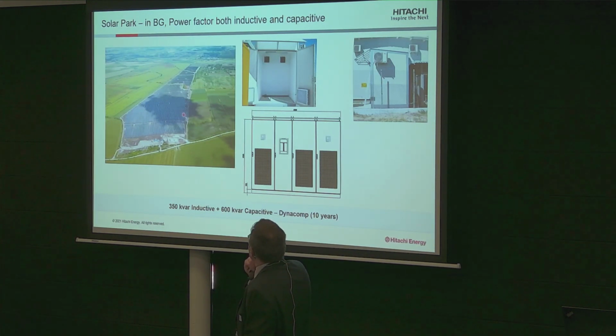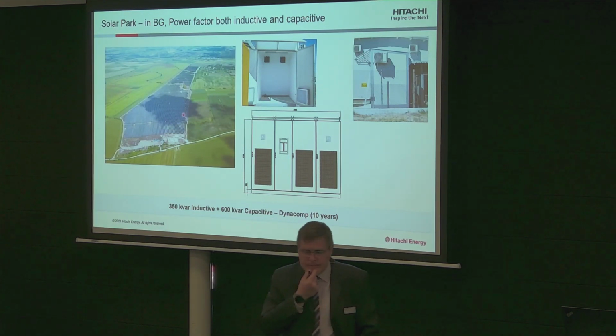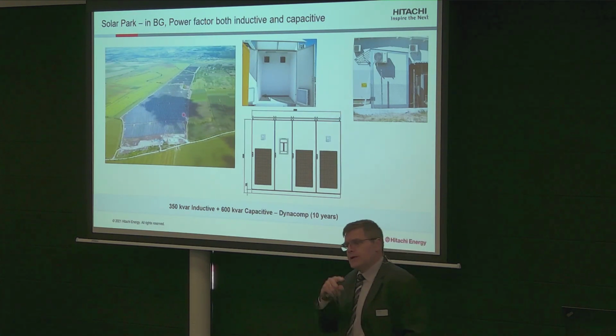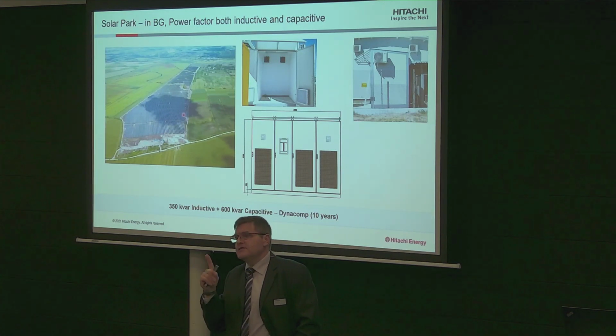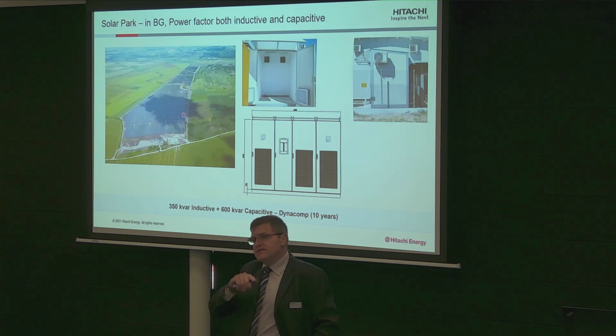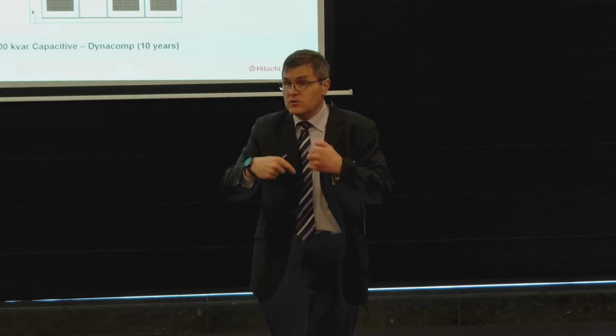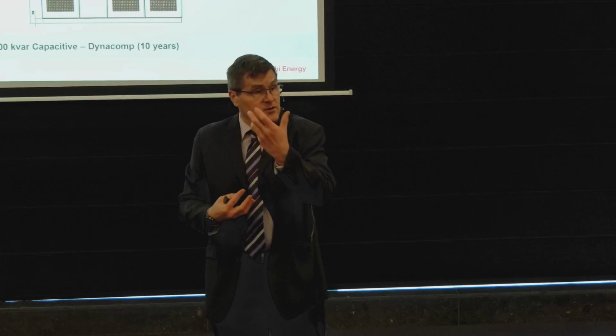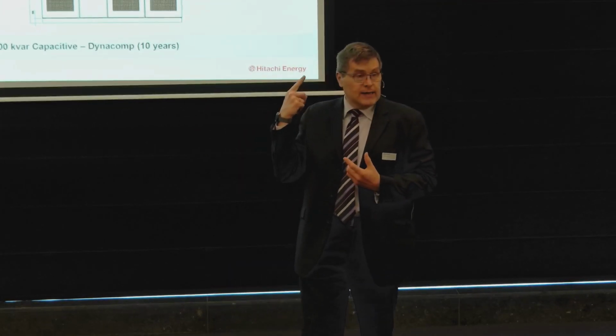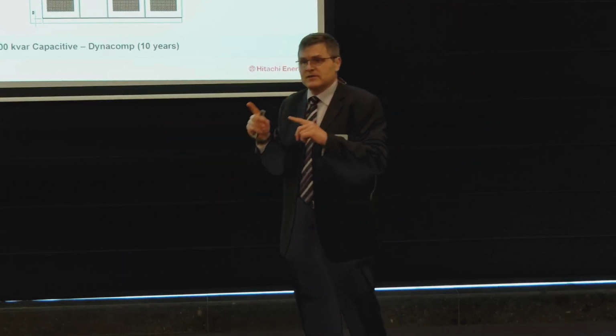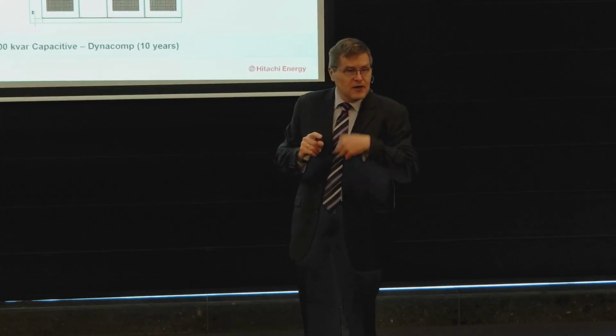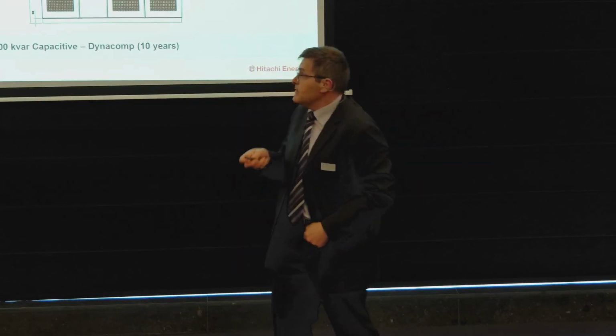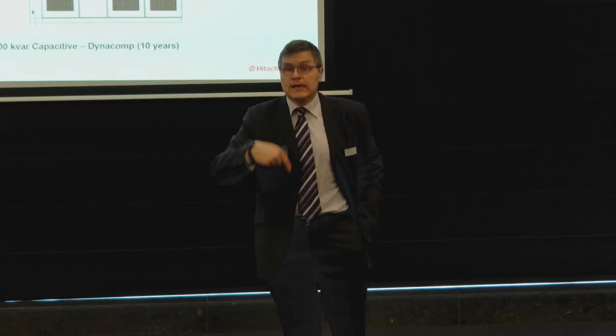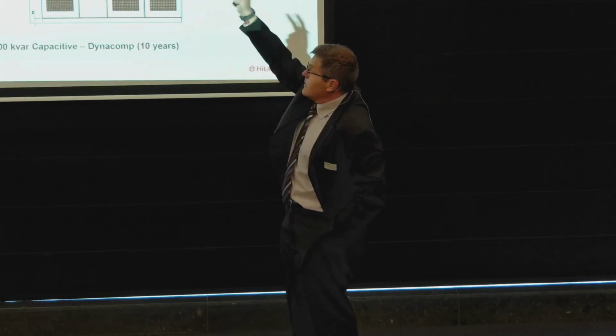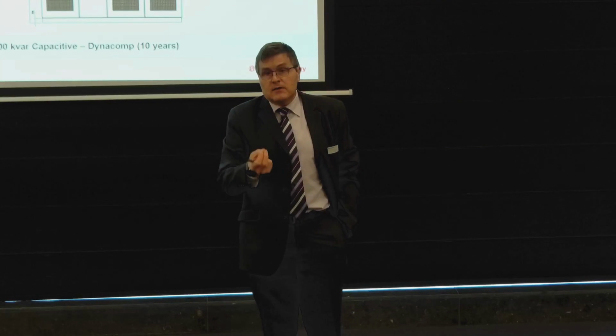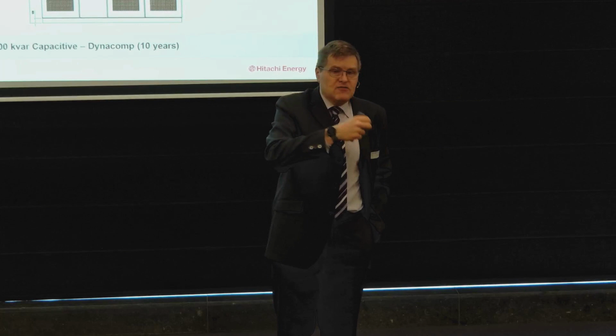Alors, this is a solar park in Bulgaria, and actually, what is the problem here is that during the night, the solar park is reactive capacitive. So in industry, we have reactive inductive load. Transformers and motors are reactive inductive because this is an induction machine. You need to create a magnetic flow. But here, during night, because of all the cables, which are basically capacitors, this is reactive capacitive. So you have two types of reactive energy, reactive leading or lagging, or capacitive and inductive. And here during night, it was reactive capacitive, but during day, when we produce power, because of the line, I don't know, it was reactive inductive. So we have on the same site, I would say, a low power factor, reactive and inductive.